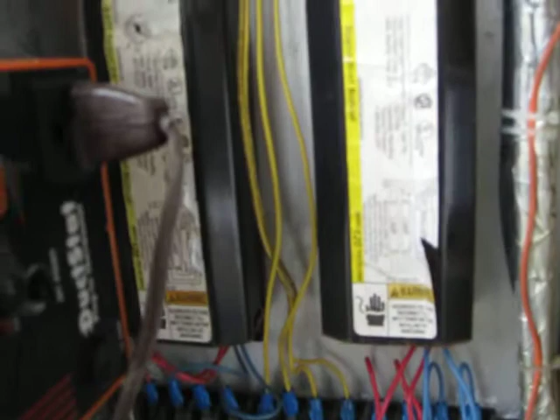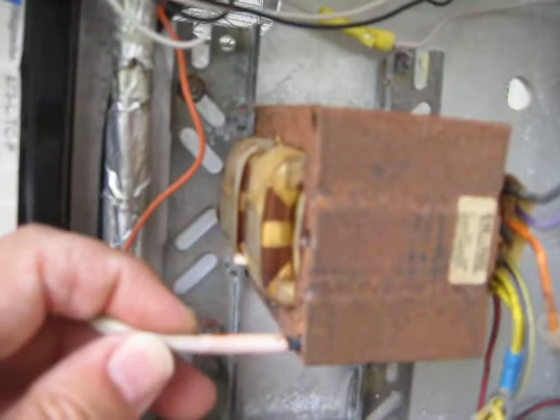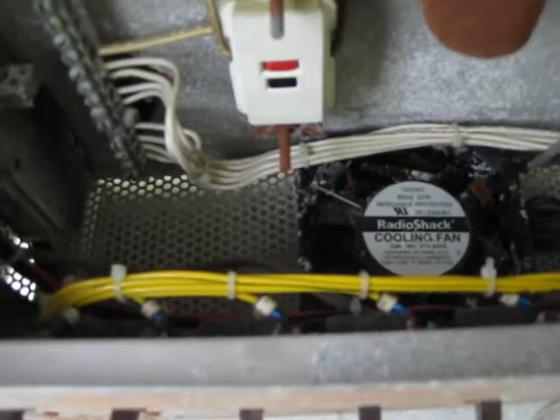The top one has a temperature probe. When the temperature in the ballast gets to a certain degree, normally 20 minutes to half an hour after it starts up, it'll get warm enough to activate the probe, and the probe activates this controller here. There's the controller. The controller turns on a fan, and the fan blows straight up through the bottom grate. You can see the bottom grate over there.